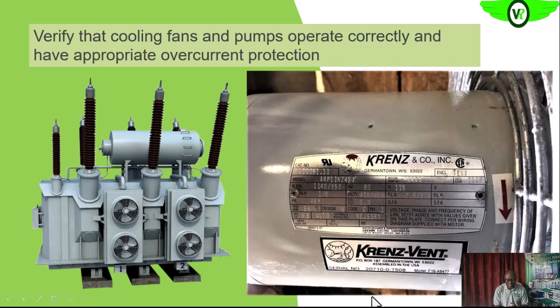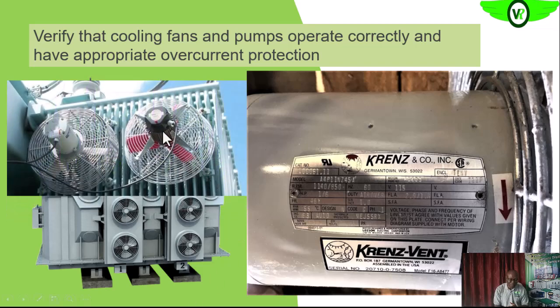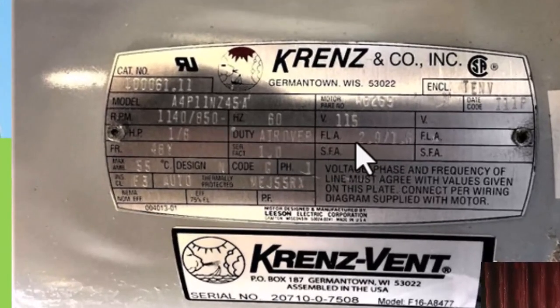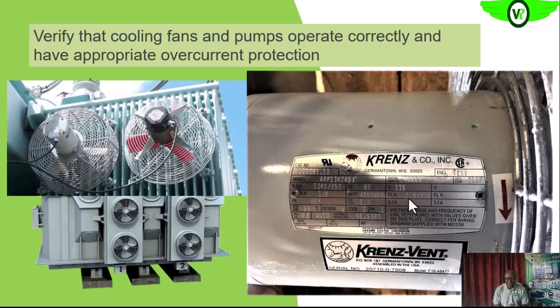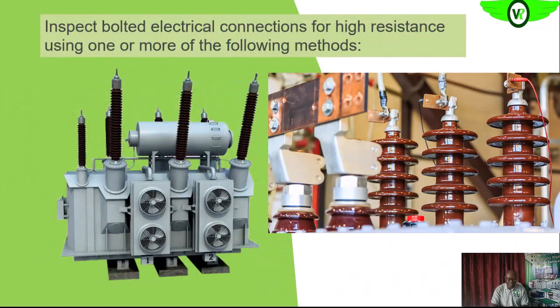So we also want to check the nameplate on the fan, okay, the cooling fan. Look at the full load current and see that an appropriate protection device is installed on that particular cooling fan, such that when the fan fails, the alarm signal will be sent to the control room, to the control operator, for the control operator to take the necessary action. Or if that fan can affect the cooling system drastically, of course, that should initiate a shutdown of the transformer. So we want to check that the appropriate overcurrent protection system is on it and they are working properly.